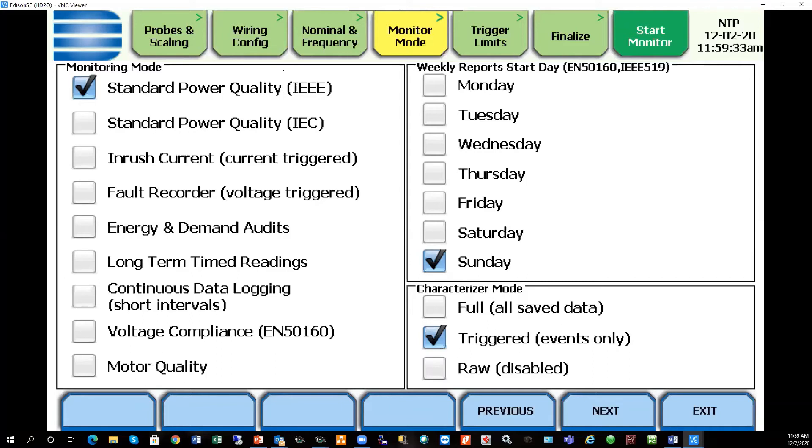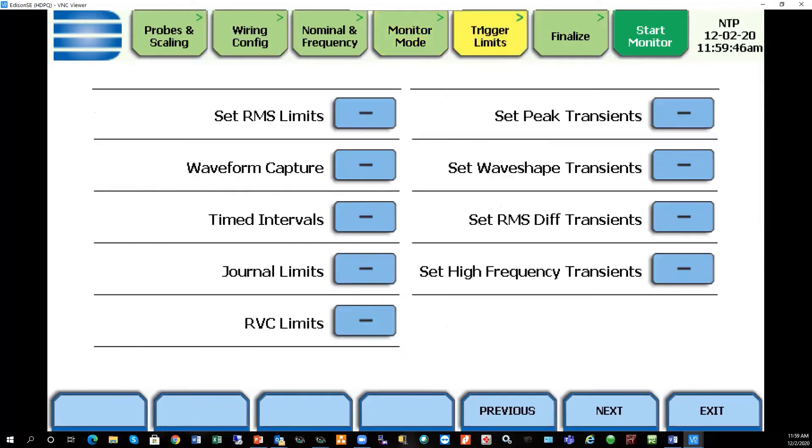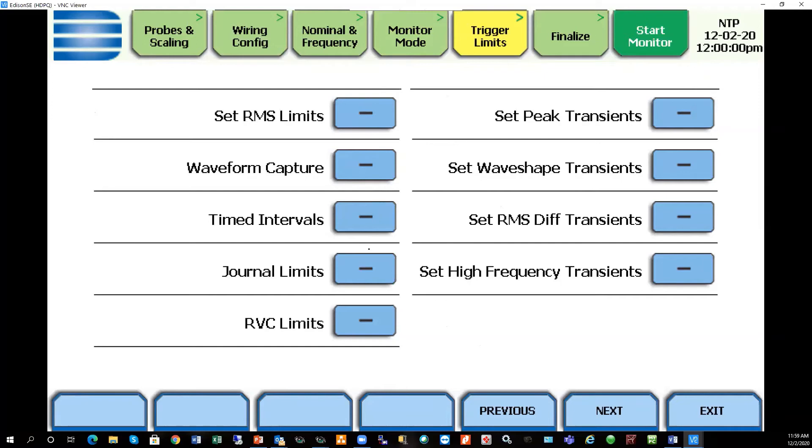Whenever you select any of the monitoring templates, if you're going to modify a monitoring template for a given application, that's all done under the trigger limits tab. You do things such as set customized limits, change your time intervals for journals and things of that nature. That's the rule of thumb: select a monitoring template to get you started. Then if you need to edit that template for any given application, you would do it in this screen here.